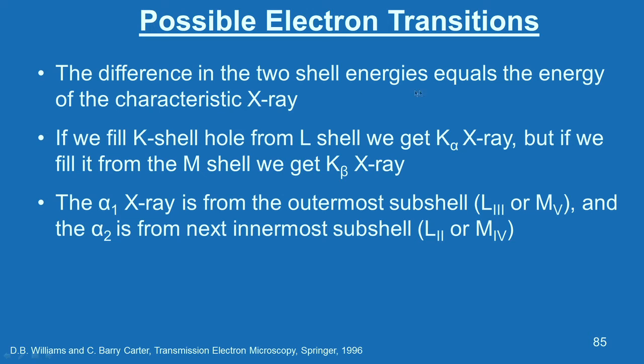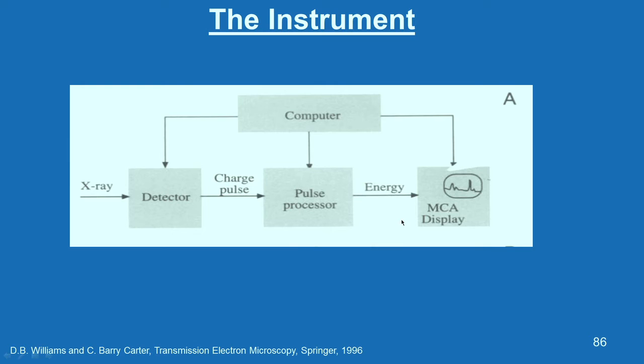The difference in the two shell energies equals the energy of the characteristic X-ray. If we fill a K shell hole from an L shell we get Kα X-ray; if we fill it from the M shell we get Kβ X-ray. The α1 X-ray is from the outermost sub-shell like L3 or M5, and α2 is from the next innermost sub-shell like L2 or M4. The instrument details: X-rays come in to the detector, producing a charge pulse fed into a pulse processor, then displayed as energy in an MCA, with everything controlled by the computer.